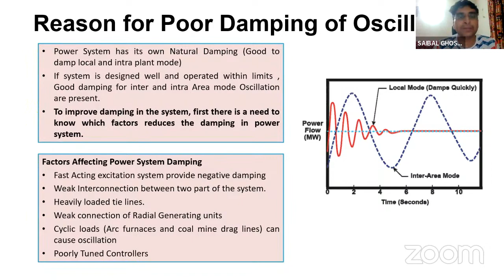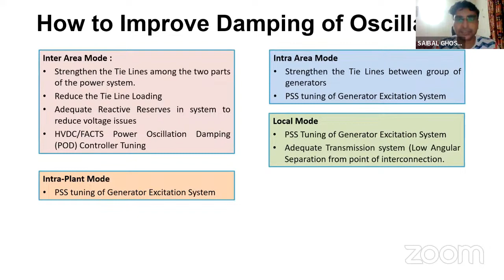So as already discussed, what tools can you use to improve the damping? You can strengthen the tie line, or you can put in more lines to improve the system strength. You can reduce the tie line loading. And most importantly, you can tune your power system oscillation damping in the FACTS and HVDC devices and the PSS in your generating unit, the generator.